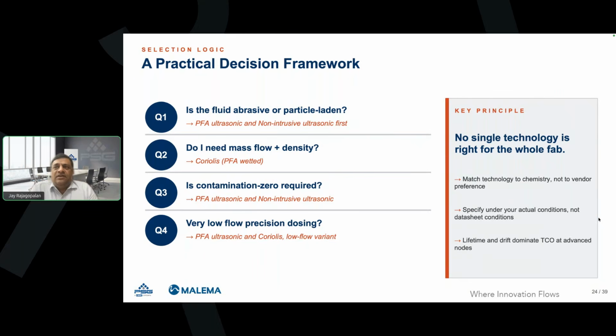Specify under your actual conditions, not datasheet conditions. For example, in some datasheets, you would have noticed that a flow controller has a 10:1 turn down ratio, that is the maximum to minimum control range. Whereas in your application, you might change the recipe so often that you may need a wider rangeability. In which case, instead of just looking at the data sheet of a product, you could interface with the vendor and figure out whether better rangeability is possible with the same device or what solutions are available. Those discussions should happen instead of just selecting from the data sheet.